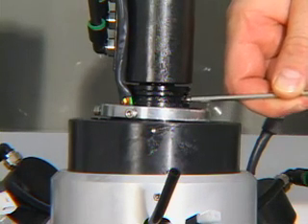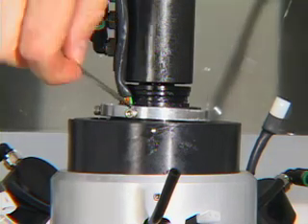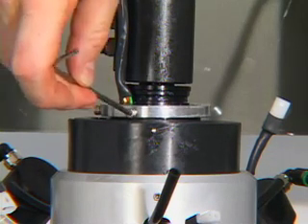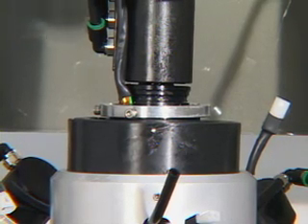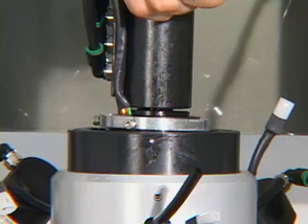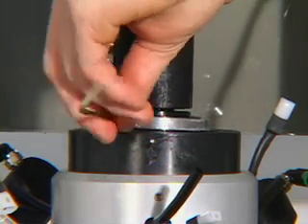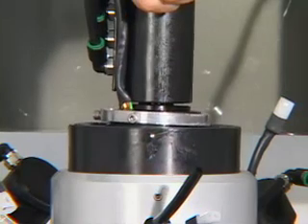Apply grease on bottom part of rotary union assembly. Push rotary union into brush block until the lock collar set bolts fit into the groove on the bottom part of the rotary union. Tighten the two allen bolts to connect the rotary union to the brush block.